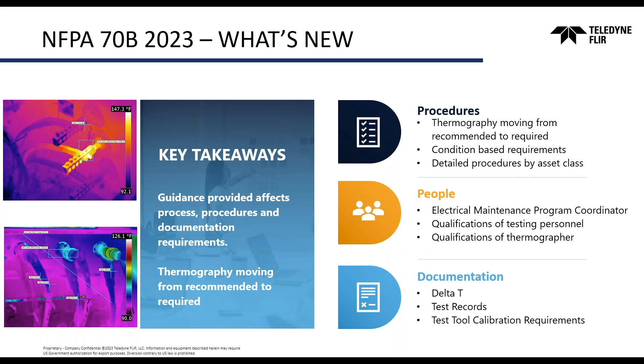Getting into the procedural side, on the right-hand side of the screen, in the blue boxes, I put in the actual section numbers for each of the areas we're talking about: 7.4.1, 9.3.1, and 9.2.2. This is directly taken from the NFPA-70B guidance. So when we reference the left-hand column, you can go pull it up and say, okay, John was discussing this in our presentation, let me go see for myself. I'm not going to read all of this to you because it's a lot to read, but I want to call it out. That recommended to required piece, as we talked about before, is in 7.4.1. In the verification of temperature, it's important to call out the two different means by which they're looking to do this.